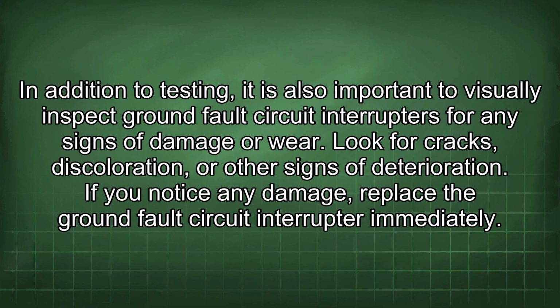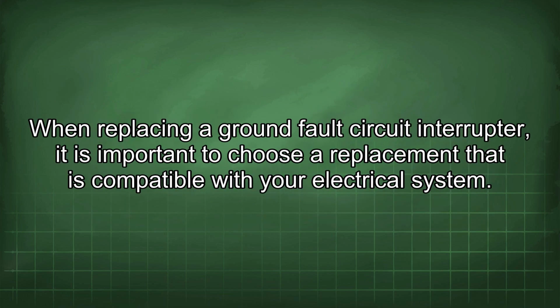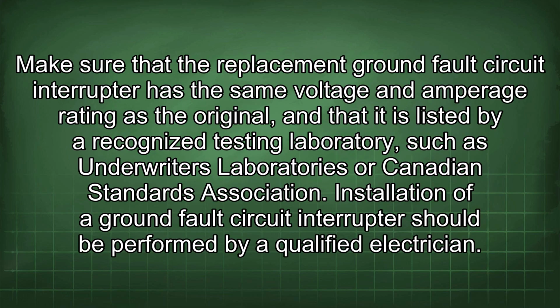In addition to testing, it is also important to visually inspect ground fault circuit interrupters for any signs of damage or wear. Look for cracks, discoloration, or other signs of deterioration. If you notice any damage, replace the ground fault circuit interrupter immediately. When replacing a ground fault circuit interrupter, it is important to choose a replacement that is compatible with your electrical system. Make sure that the replacement ground fault circuit interrupter has the same voltage and amperage rating as the original, and that it is listed by a recognized testing laboratory, such as Underwriters Laboratories or Canadian Standards Association.